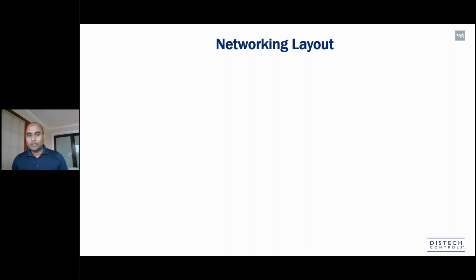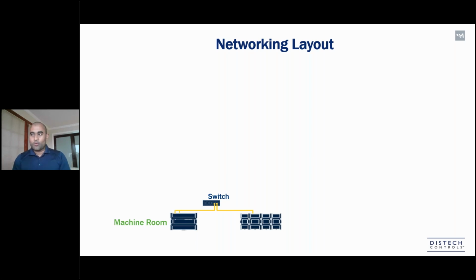Once you have the fundamental building block, it's about building up the network, getting your machine room together, getting all the chiller and HVAC components into the controllers working together. This is an IP system, so every time you have a certain number of controllers or networks together, you start to have switches there. This is very different from an MSTP system, which does not rely on switches. When you start adding switches and look at IP level control, you get much better security and much better control over the whole system.